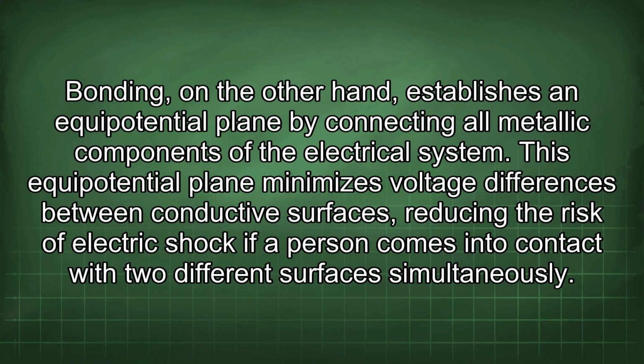Bonding, on the other hand, establishes an equipotential plane by connecting all metallic components of the electrical system. This equipotential plane minimizes voltage differences between conductive surfaces, reducing the risk of electric shock if a person comes into contact with two different surfaces simultaneously.